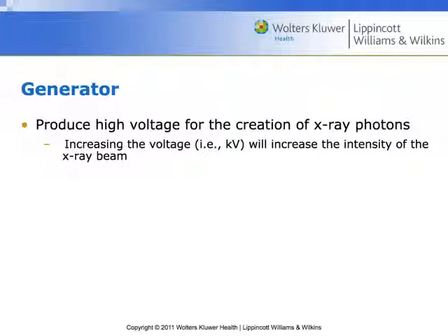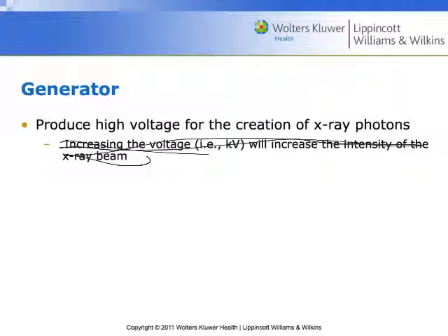The textbook states that increasing voltage KV increases x-ray beam intensity and thereby reduces patient dose — this is simply not true for CT. It was a belief that came out of diagnostic x-ray. Current research tells us this is not the case anymore because of the computational part of CT. The two big areas driving CT research right now are largely the computational parts, since the hardware — the gantry — is pretty stable.